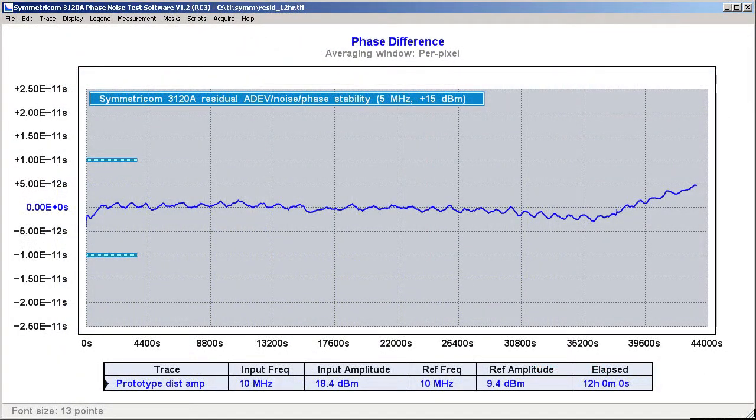This trace reveals the amplifier's long-term stability over the entire 12-hour period. The observed phase drift over that period is less than 10 picoseconds. We can see the effect of thermal cycling from the air conditioning with a period of about 20 minutes. We can't be 100% sure whether the amplifier or the 3120A itself is dominating this measurement, but in either case the performance is just superb.